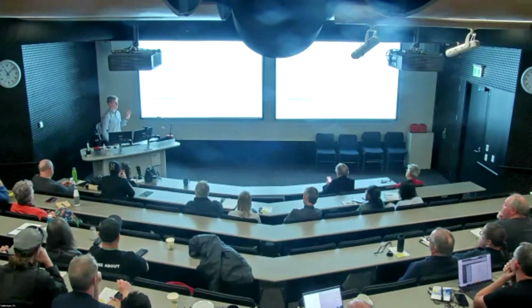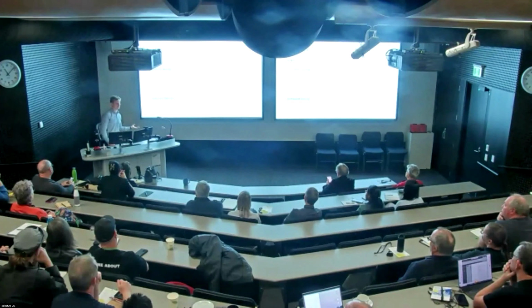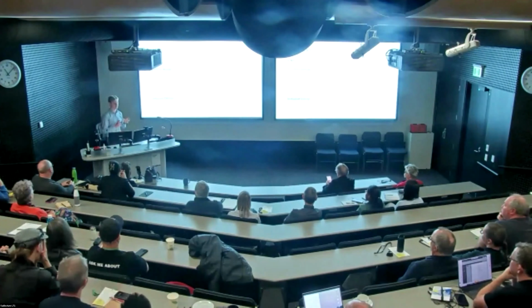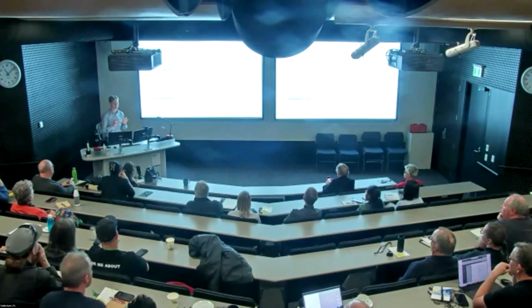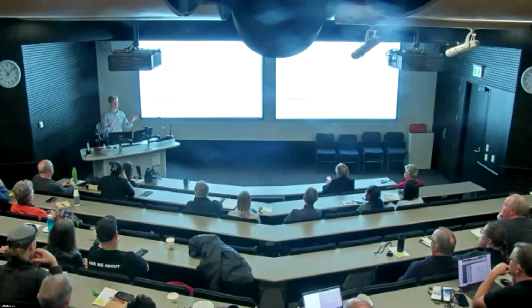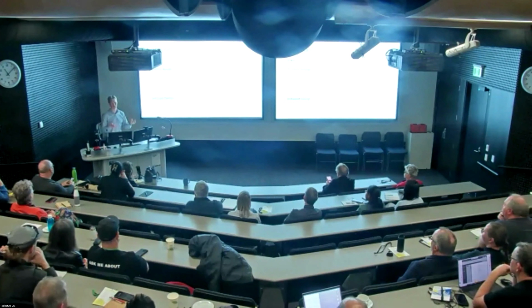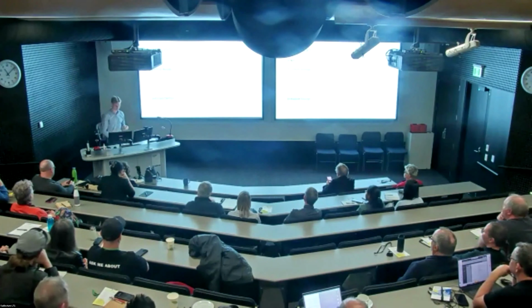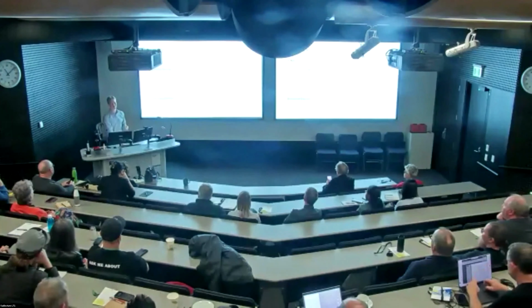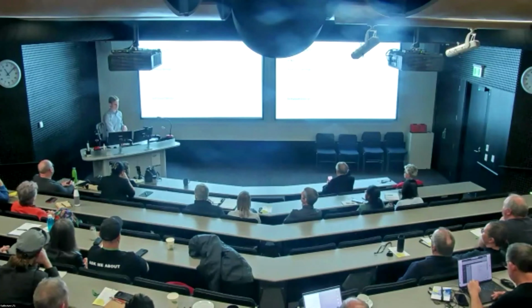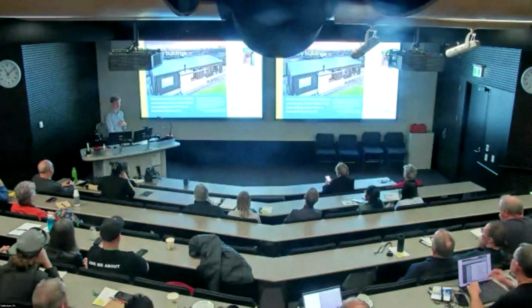As noted, if you're in Wellington and think the peak might be in the late afternoon for the whole building, be cautious. Early on in the design, you could apply a multiplier to those perimeter zones as an initial sizing estimate, so you're not spending tons of your client's money to get a zonal cooling estimate really early on. But for a detailed design, we would recommend using zonal cooling loads. And yeah, that's that.